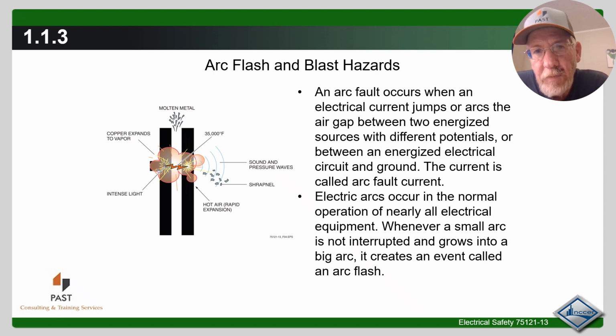An arc fault occurs when an electrical current jumps or arcs the air gap between two energized sources with different potentials, or between an energized electrical circuit and ground. The current is called arc fault current. Electrical arcs occur in the normal operation of nearly all electrical equipment. Whenever a small arc is not interrupted and it grows into a big arc, it creates an event called an arc flash.